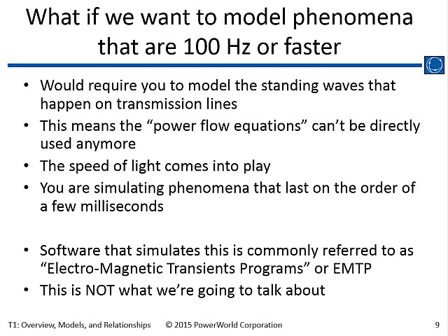When you solve the power flow, you're solving a set of algebraic equations, saying that across my grid I have this power balance that occurs everywhere. That's not taking into account transmission system delays because of speed of light effects, because in a power flow they don't come into play. When you start getting down into the shorter time scale, you have to do that, and that's what something called the Electromagnetic Transient Program, or EMTP, does, which BPA played a big role in the development of that software.